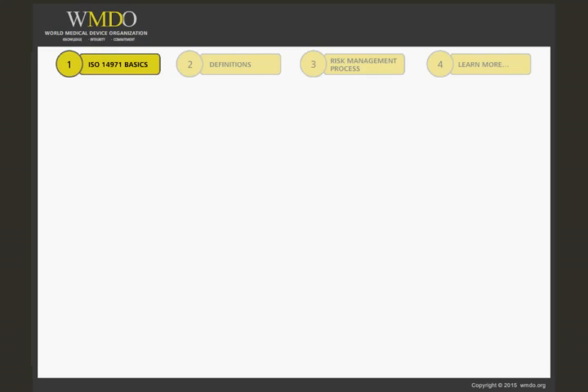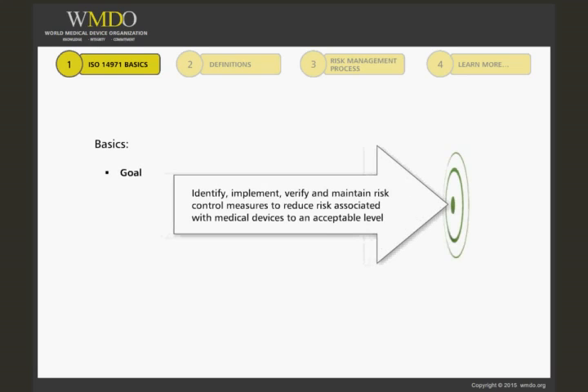Summarizing the standard in a few headlines reveals the following basics. The overall goal of the standard is to identify, implement, verify, and maintain risk control measures to reduce to an acceptable level the risk associated with medical devices.